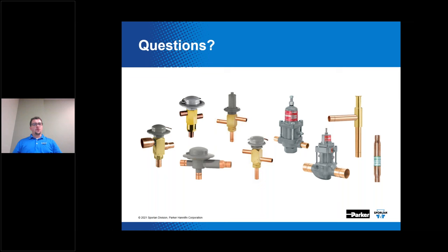Thank you, Adam, for the presentation — it was really informative. I just wanted to clarify the answer to the last poll question: True — the receiver provides a way of storing the added charge required for condenser flooding during the summer. Now we have a couple of questions.